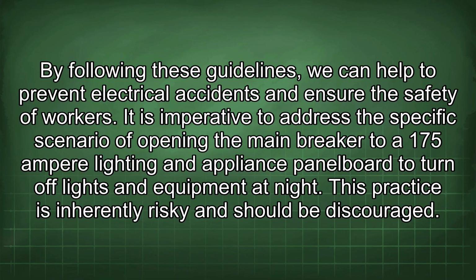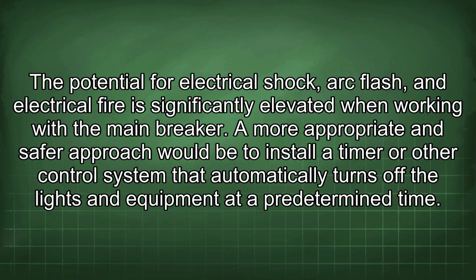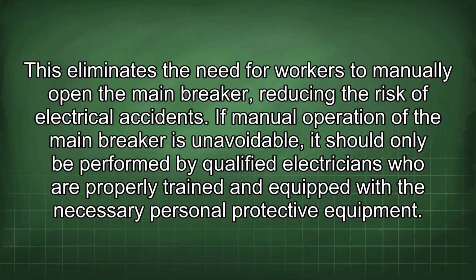It is imperative to address the specific scenario of opening the main breaker to a 175 ampere lighting and appliance panel board to turn off lights and equipment at night. This practice is inherently risky and should be discouraged. The potential for electrical shock, arc flash, and electrical fire is significantly elevated when working with the main breaker. A more appropriate and safer approach would be to install a timer or other control system that automatically turns off the lights and equipment at a predetermined time. This eliminates the need for workers to manually open the main breaker, reducing the risk of electrical accidents.